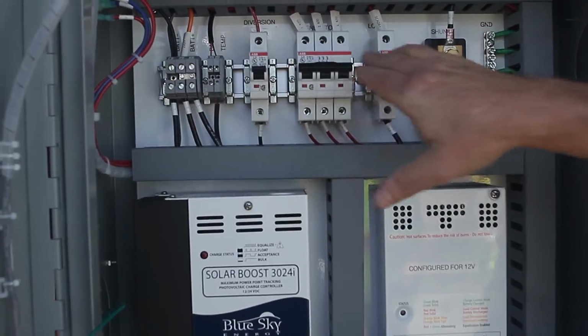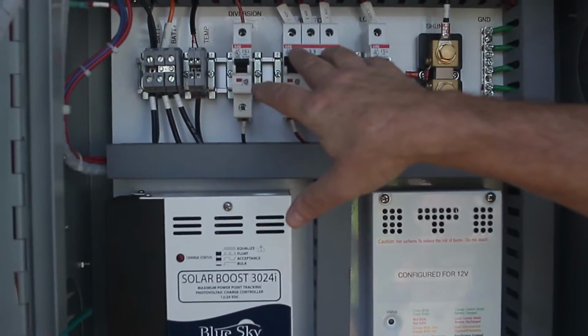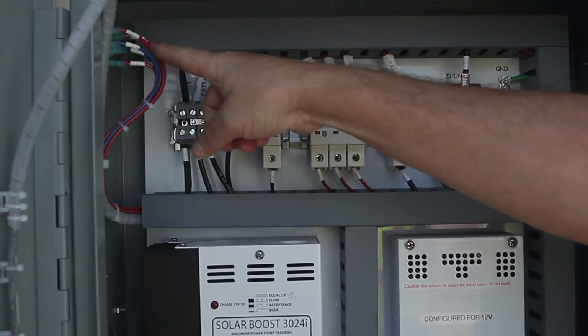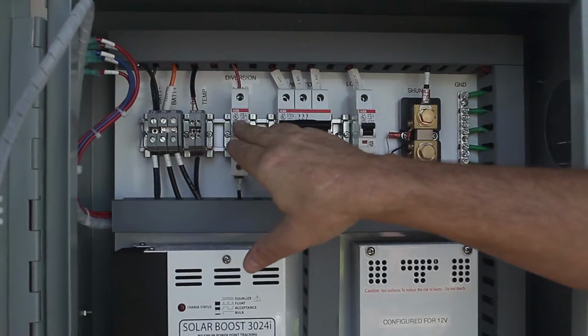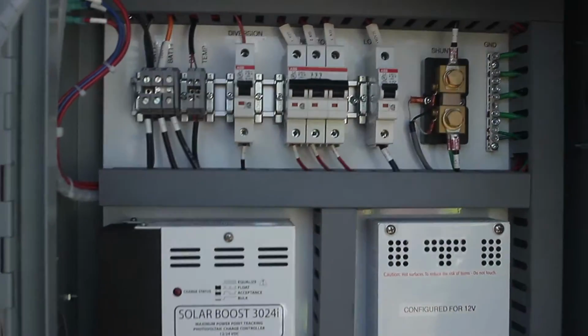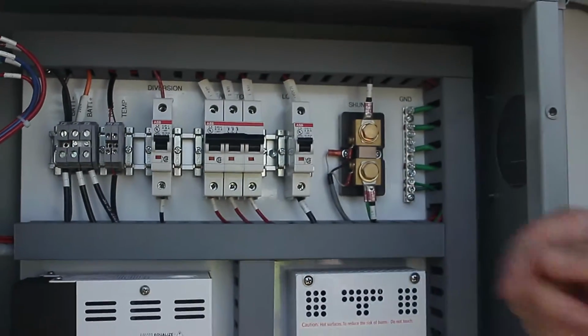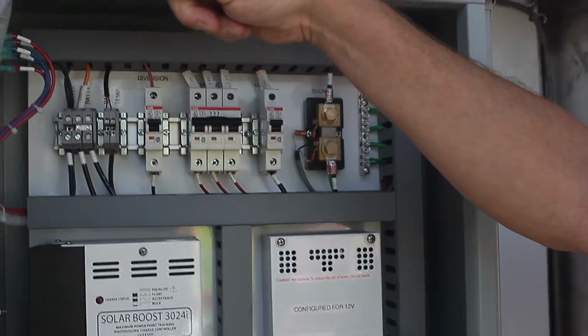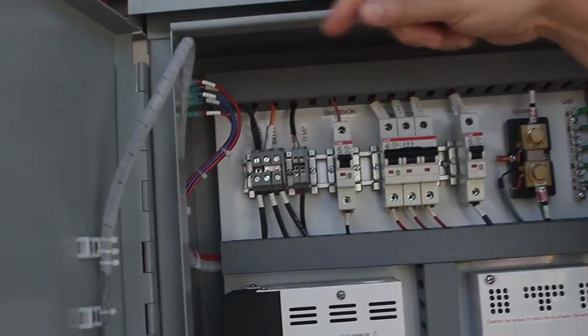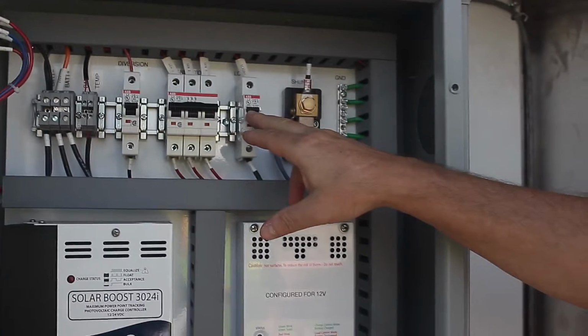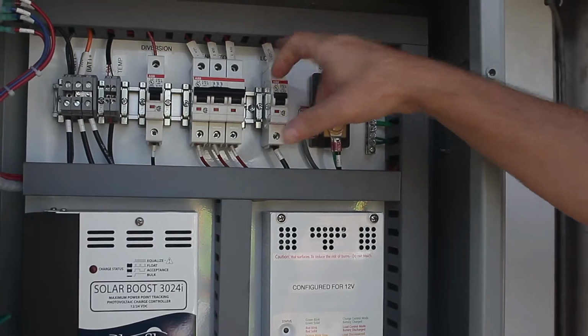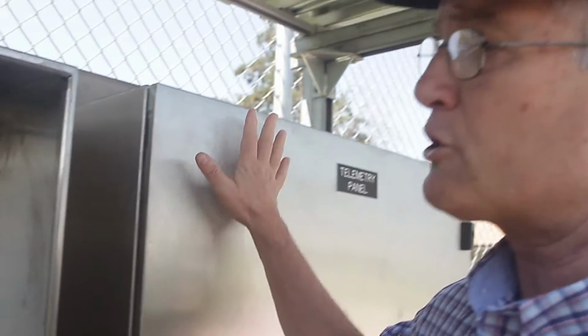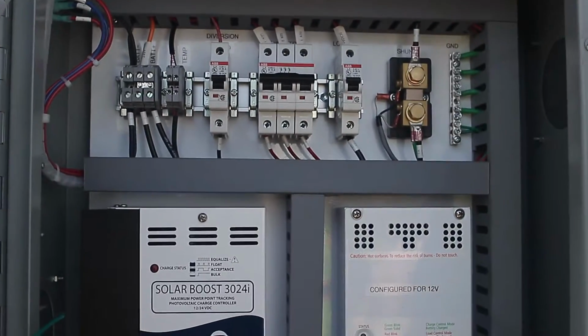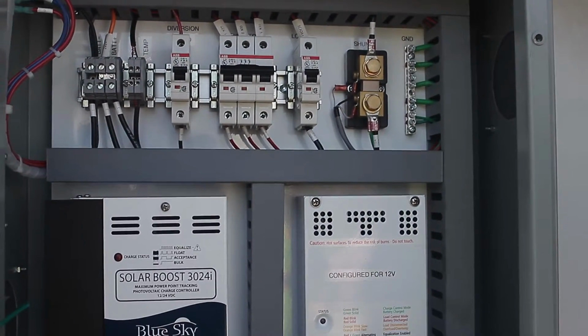Here on the circuit breakers, we have the AC coming in from the generator to the DC rectifier. The diversion load, which is a heater we'll look at next: when the batteries are full, the generator keeps running and diverts the energy to a diversion load heater next to our panel here. The load itself, 24 volts, they're running their SCADA off to the side here. We'll go into that next. So that's the 24 volts powering all of the SCADA and instrumentation.